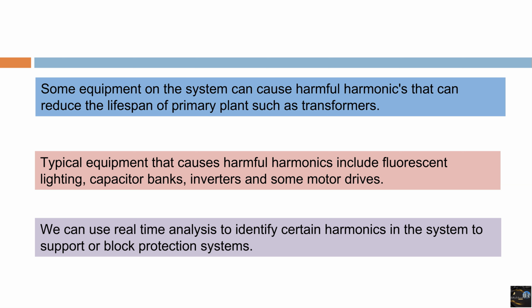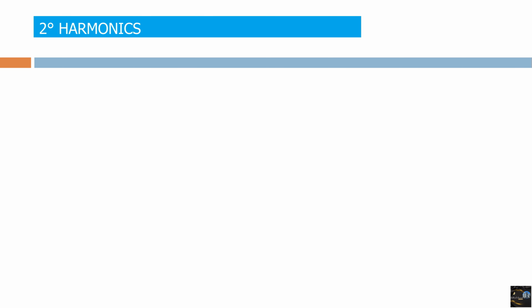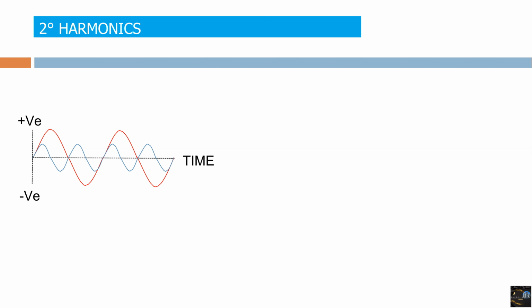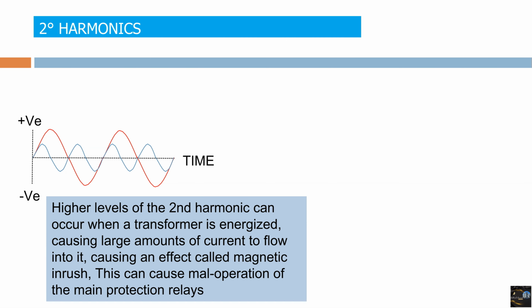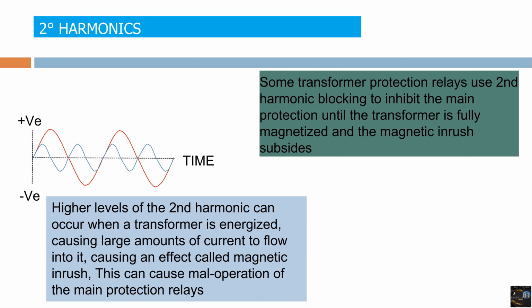So first comes our second harmonic. You can see a higher level of the second harmonic can occur when a transformer is energized, causing large amounts of current to flow into it, causing an effect called magnetic inrush. This can cause maloperation of the main protection relays. Some transformer protection relays use second harmonic blocking to inhibit the main protection until the transformer is fully magnetized and the magnetic inrush subsides.